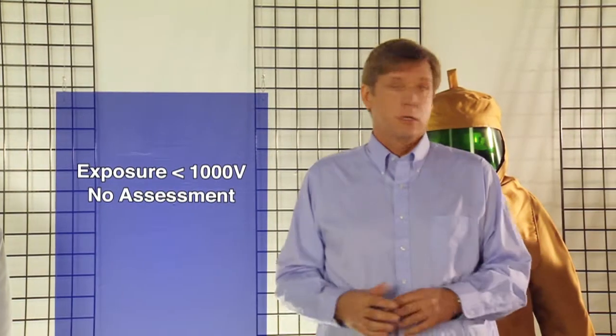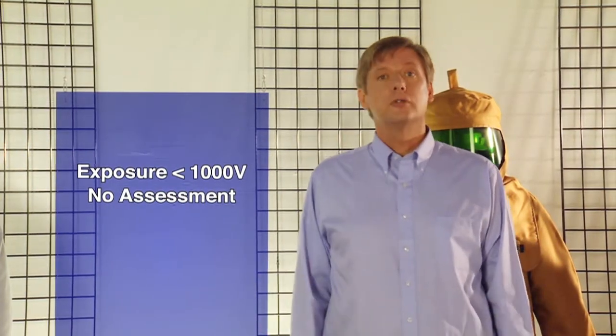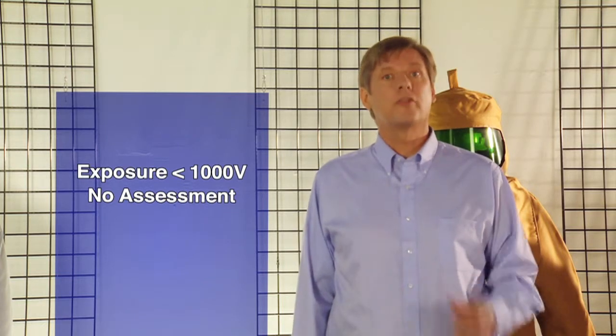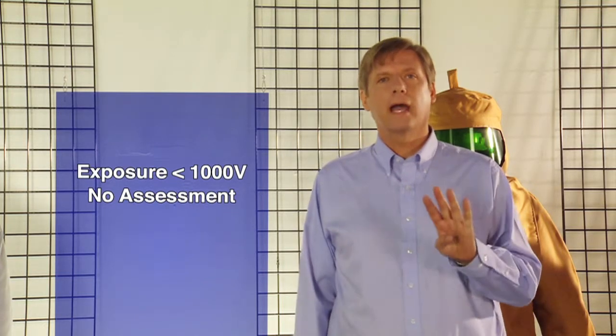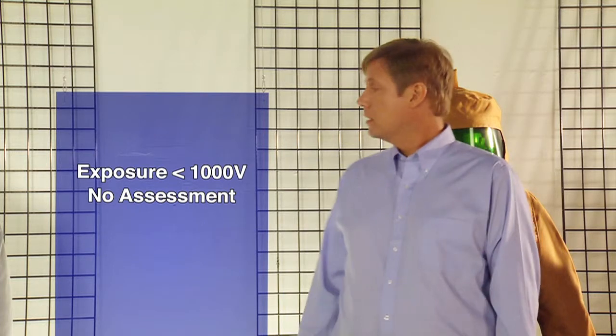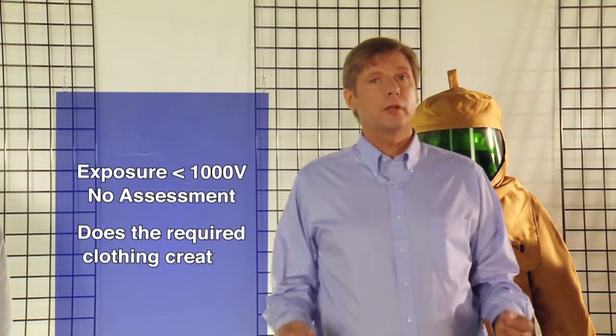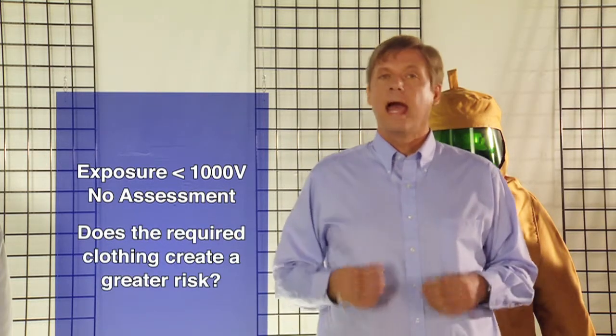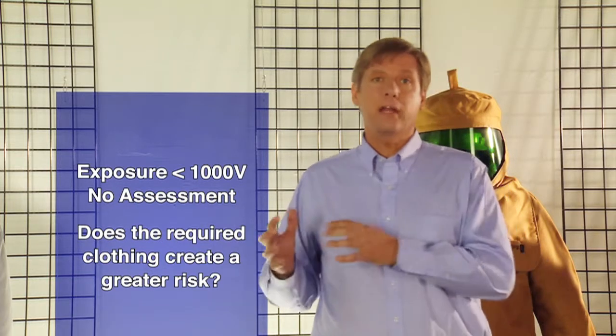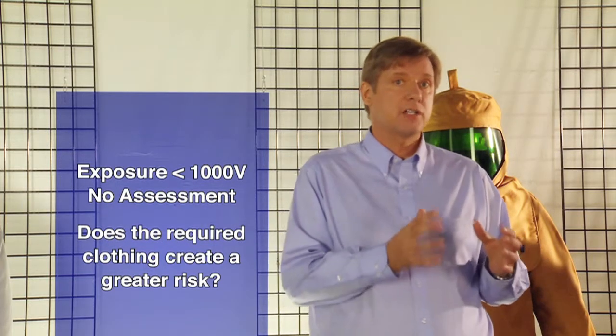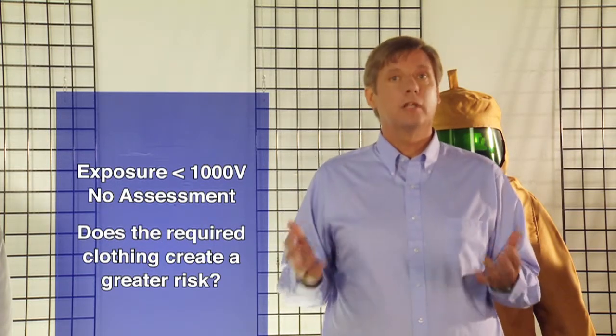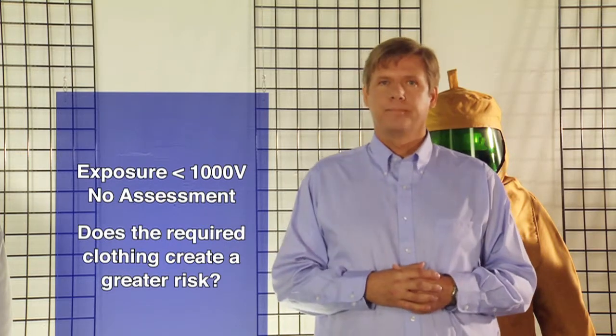First, if the exposure is below 1000 volts, no assessment is required. You just need to put workers into clothing with a minimum arc rating of 4 calories per square centimeter. Second, if the clothing required to meet a particular level has the potential to create a greater hazard for the worker than the arc flash hazard itself, then clothing of a lower arc rating may be worn.